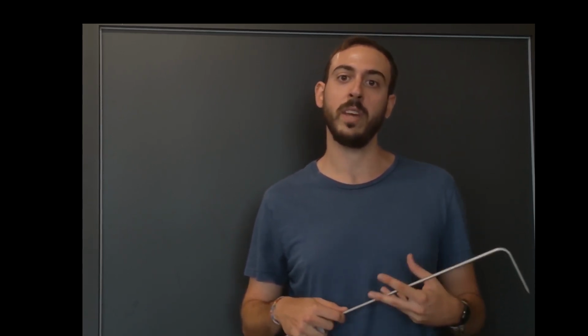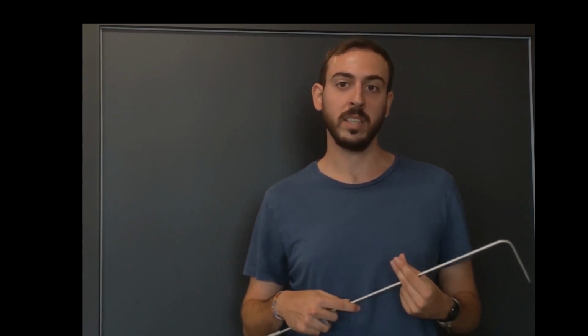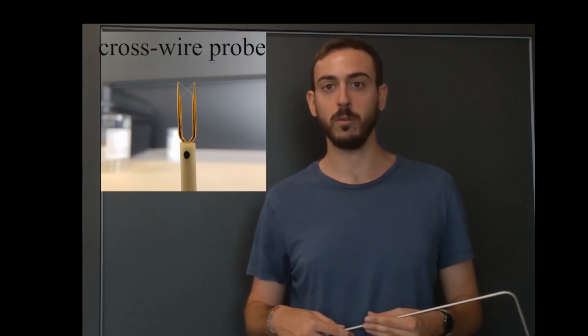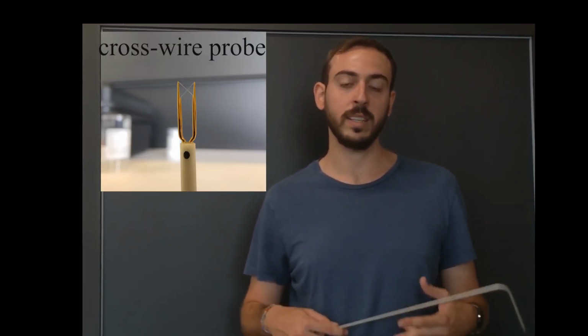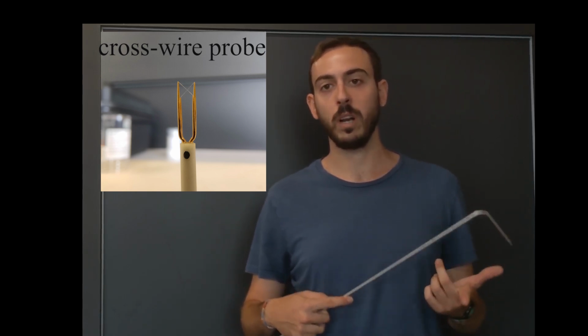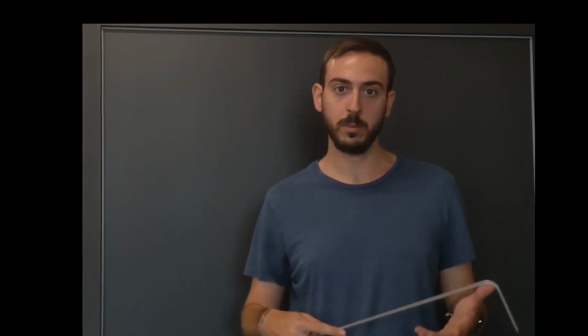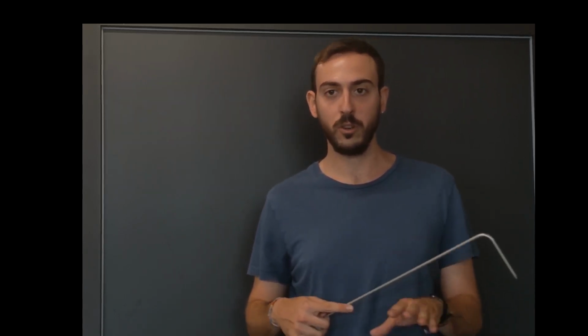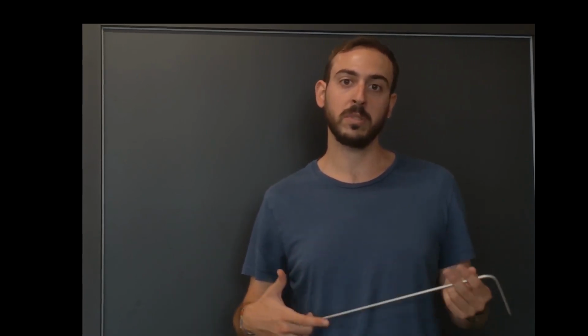Note that the hot wire probe only measures the magnitude of the velocity vector normal to the wire axis. This means that a single wire probe cannot distinguish between different velocity components. To do so, we have to employ a so-called cross-wire probe that contains two or more wires at an angle. To calibrate this kind of sensor, we have to repeat the voltage-velocity characterization for different yaw angles. So the procedure becomes time-consuming and tedious.